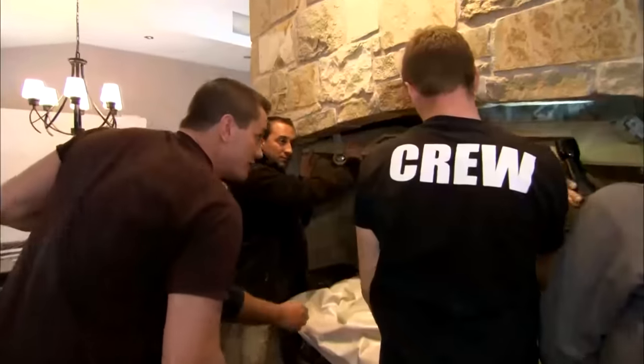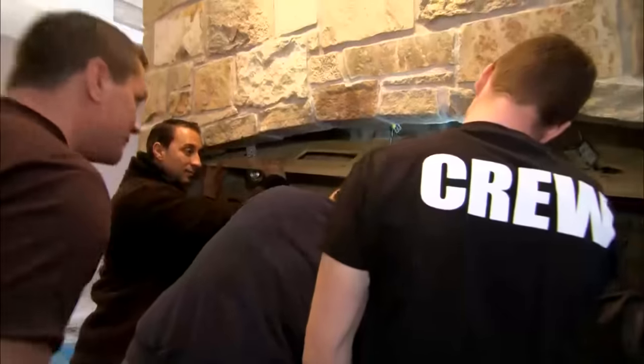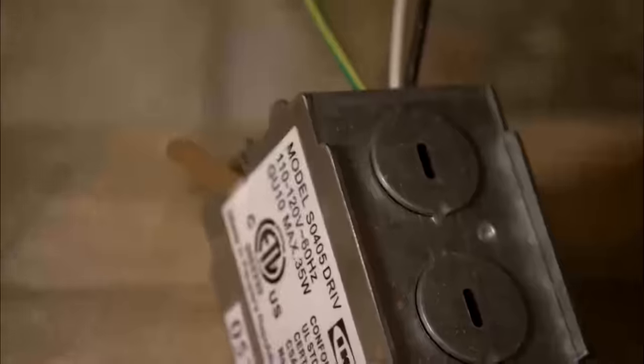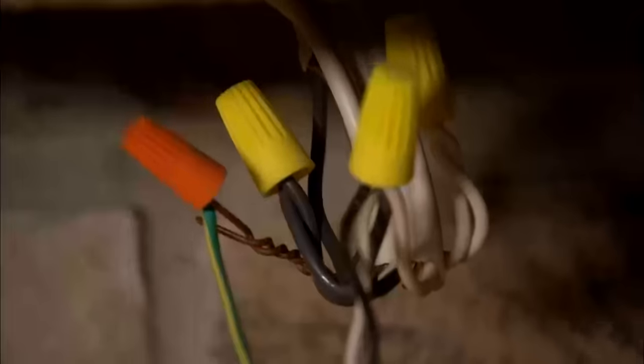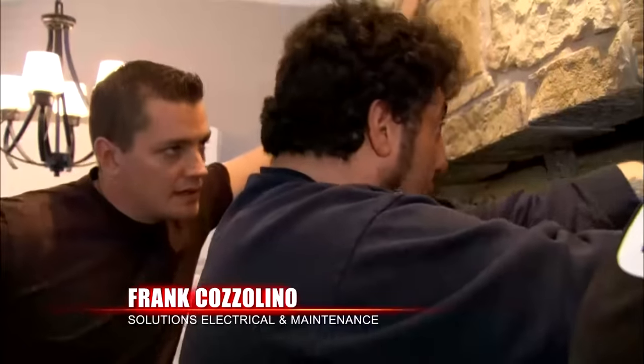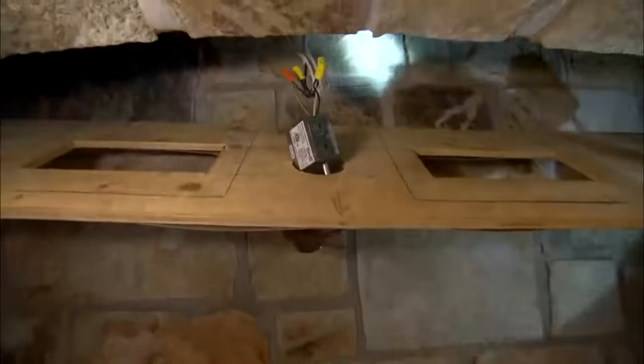Look at this — I just wanted to show you what they've done with these pot lights. Are you kidding me? No. You see the fraying that's already happening on that cable? That's from this cable rubbing against the metal, which is sharp. So this is just a matter of time — it's going to short out against the metal. This is grounded through this cable, which is going to cause a dead short. Look at the three lines just hanging in the middle of nowhere, all bundled up right here. Disgusting. It's called an open air connection.